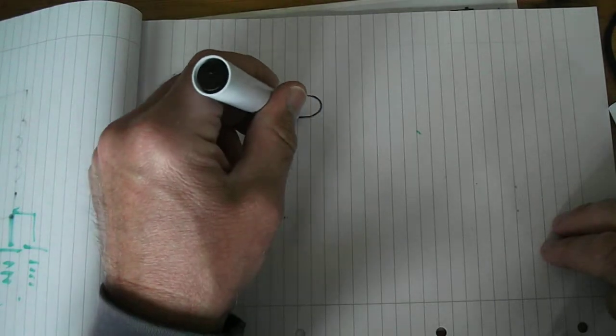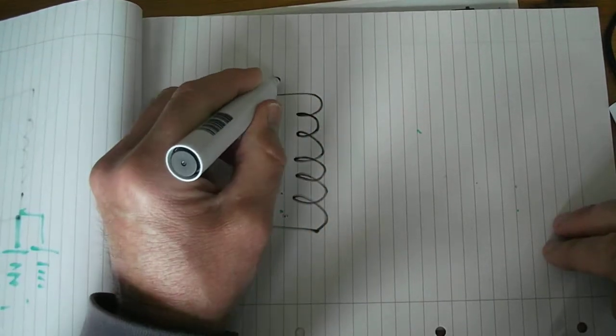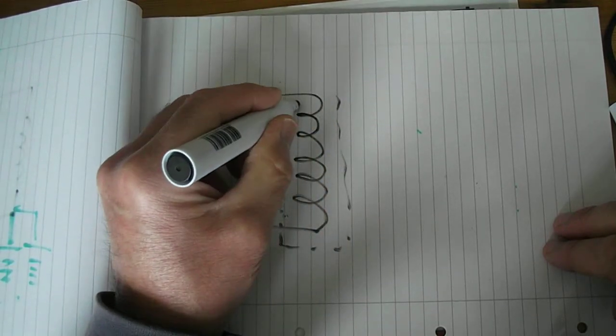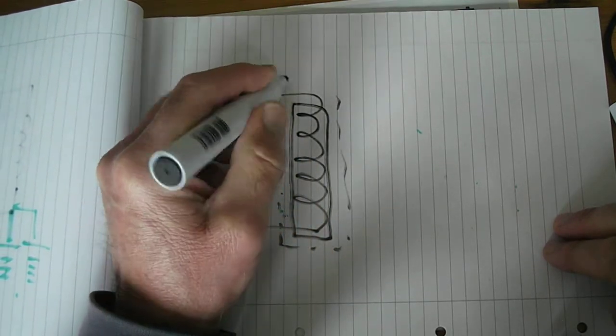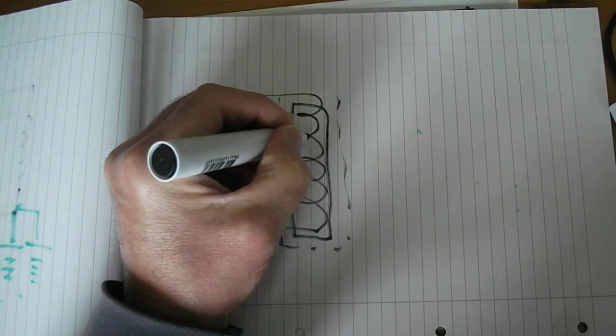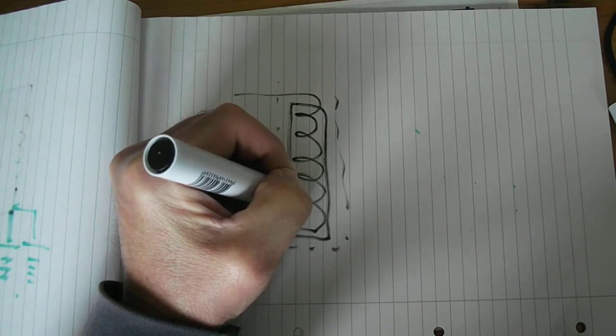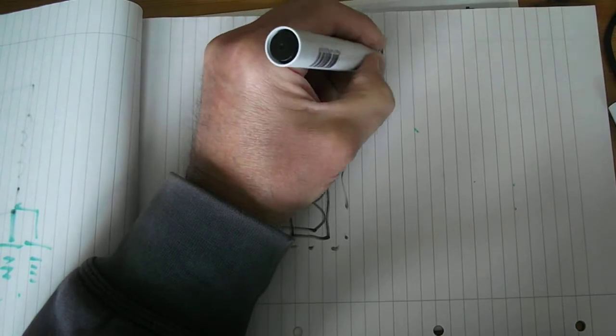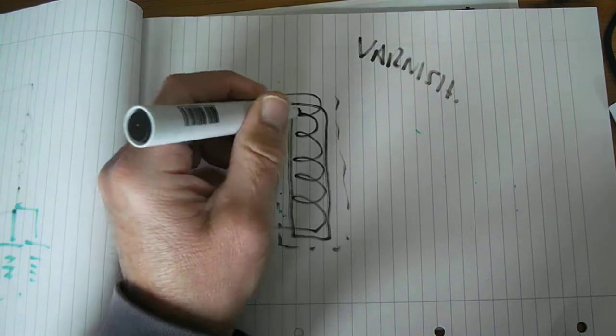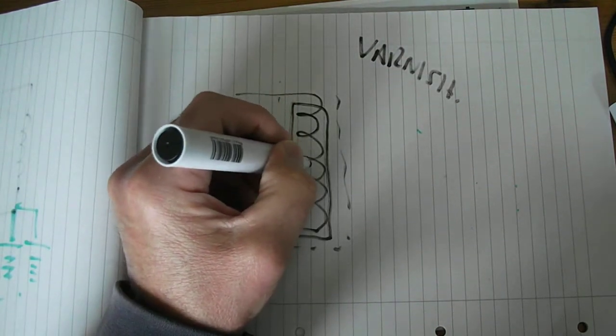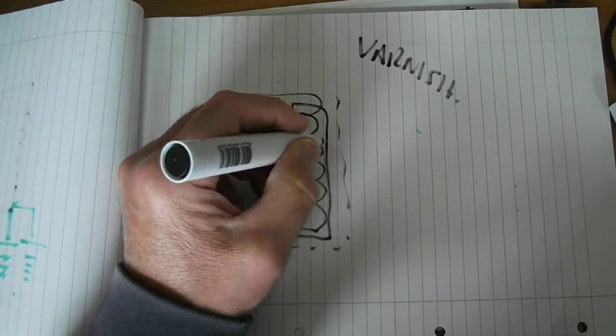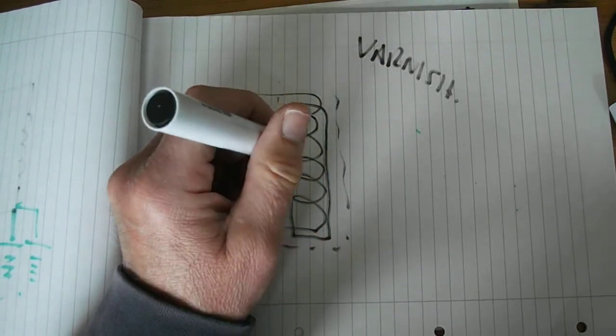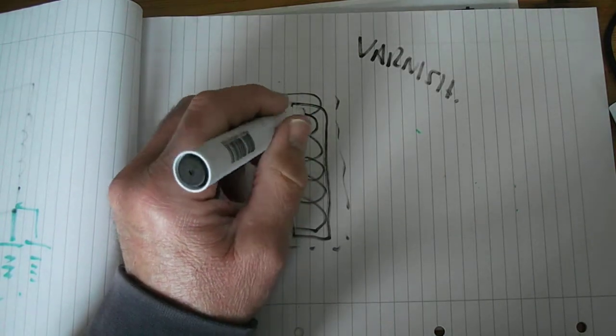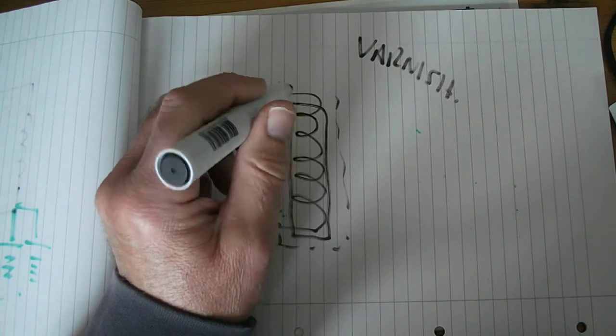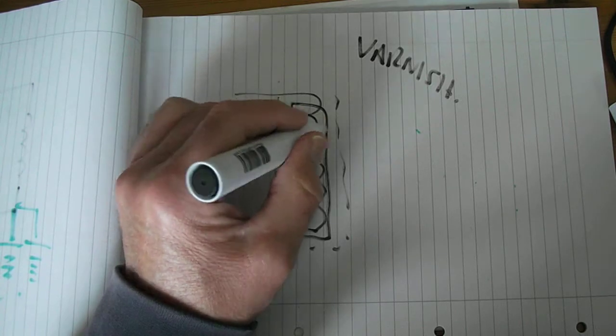Transformer windings. The winding of a transformer, because it's tightly wound around the core, the insulation on this winding coil has to be very thin, and the thinnest way to do that is to use varnish. It's actually now a plastic, a very fine plastic film that they use on the winding, but it's very, very thin. Traditionally, it was what we call a varnish, but it's not like a wood varnish. It's a bit more sophisticated than that. It's specially developed to have high insulation properties. It's got a very high dielectric strength when it dries on the winding.